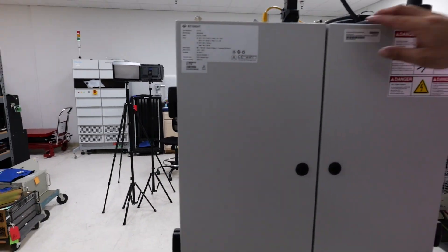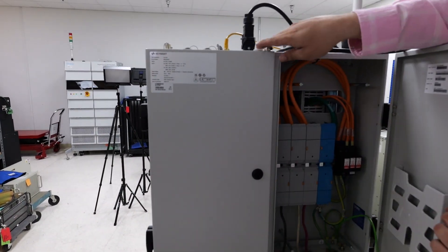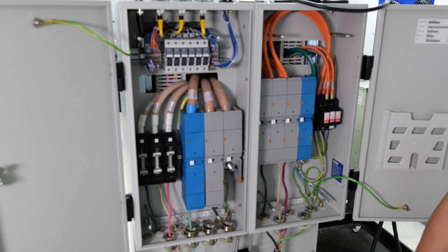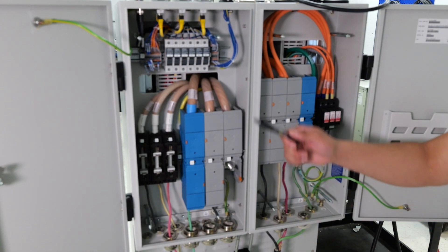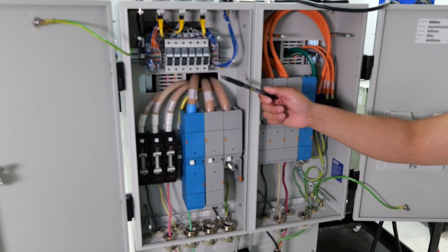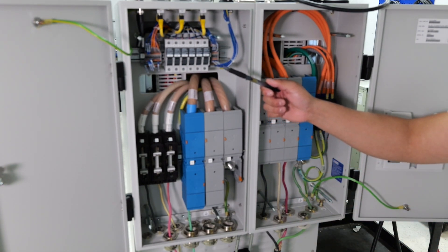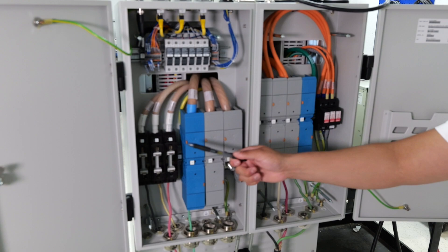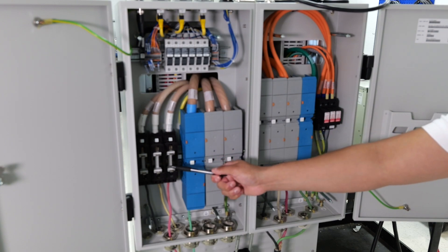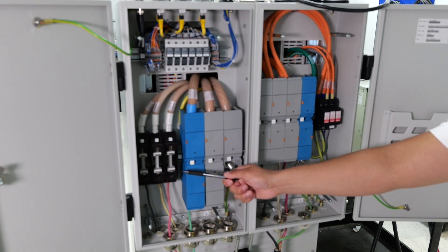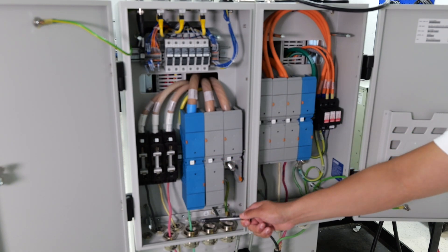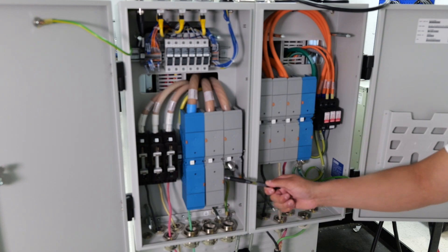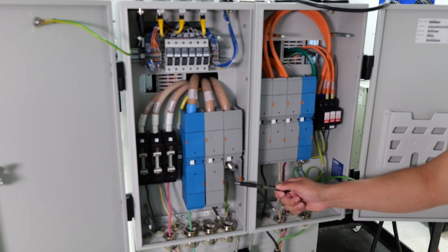Now let's take a look at our input and output connections. This here is the output. It's a three-phase, five-wire connection - lines 1, 2, and 3 with neutral and ground. We also have separate DC positive and negative outputs as well.